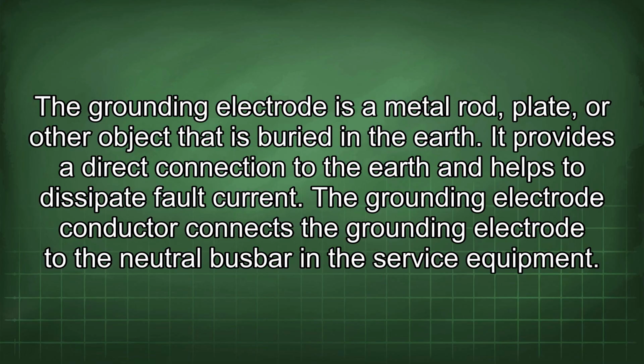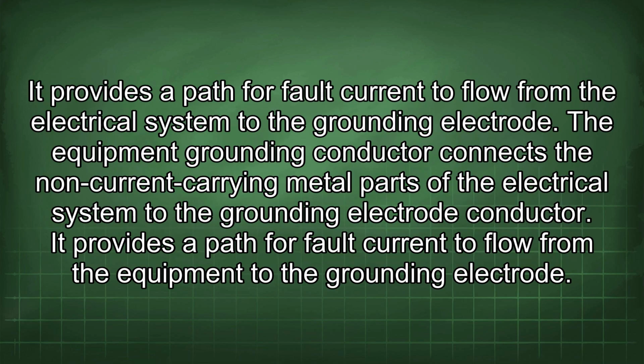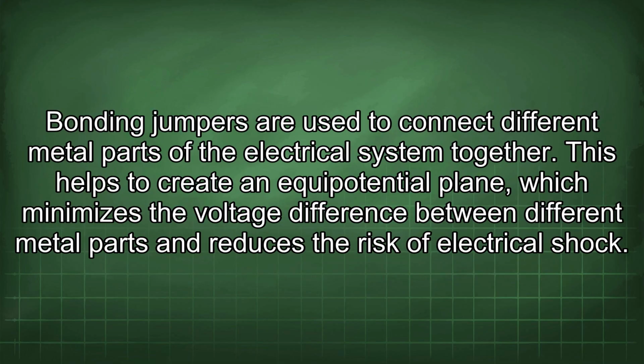It provides a direct connection to the earth and helps to dissipate fault current. The grounding electrode conductor connects the grounding electrode to the neutral busbar in the service equipment. It provides a path for fault current to flow from the electrical system to the grounding electrode. The equipment grounding conductor connects the non-current carrying metal parts of the electrical system to the grounding electrode conductor. It provides a path for fault current to flow from the equipment to the grounding electrode. Bonding jumpers are used to connect different metal parts of the electrical system together. This helps to create an equipotential plane, which minimizes the voltage difference between different metal parts and reduces the risk of electrical shock.